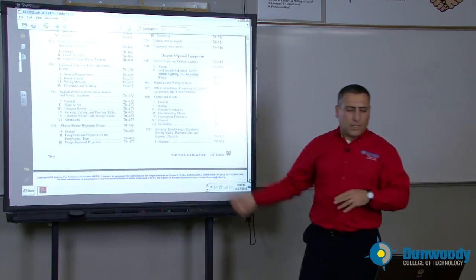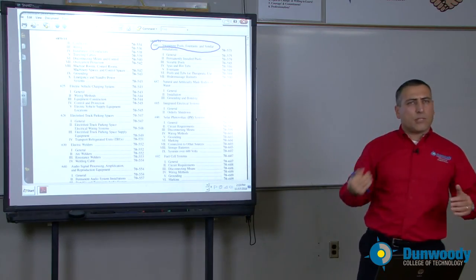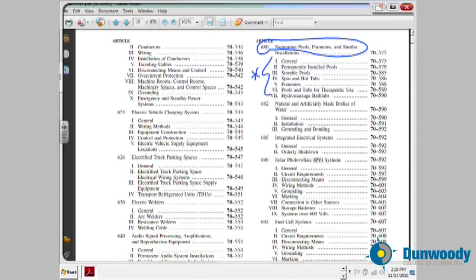Moving from special occupancies into special equipment — the NEC code singles out certain equipment with special rules, where chapters 1 through 4 apply only if referenced. You can see electric signs, cranes, elevators, manufactured wiring, and welders — all special equipment needing special attention. One of the most important is the swimming pool article. If you have to wire a swimming pool, it's different than wiring your bedroom. The swimming pool article covers what type of wire to use, how to ground the pool, and how to design the equipotential grounding system. This applies to swimming pools, fountains, and spas.